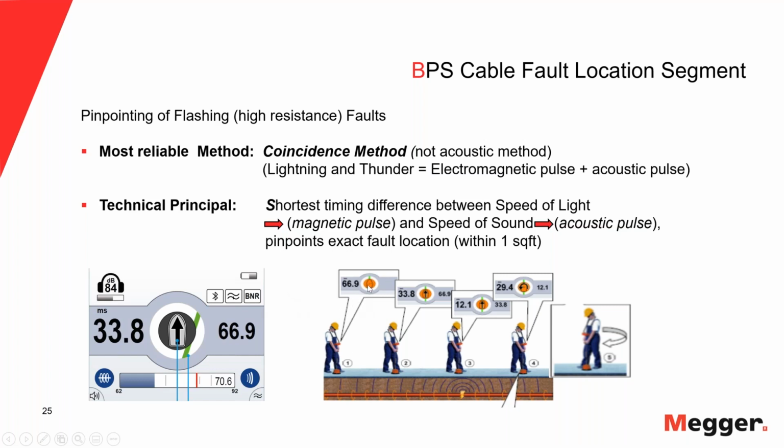If you look at this gentleman down here on the far left side, where it says 66.9 milliseconds. So he has a stopwatch, and it has two sensors, the electromagnetic sensor and the acoustic sensor. When it picks up the electromagnetic pulse, it starts the stopwatch, and when it picks up the acoustic, it stops the stopwatch and gives you the timing.